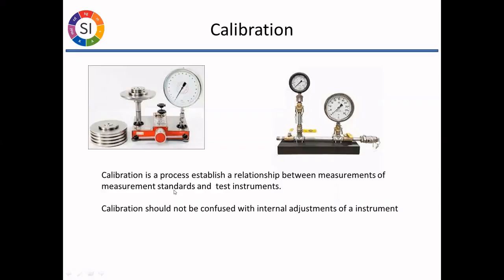We can find a term called internal calibration in the manuals of some industrial instruments. Actually, it is a self-internal adjustment. So we should not confuse it with calibration. After calibration, we get a calibration certificate that shows indicator values of the testing instrument traceable to SI units through an unbroken chain of calibrations. The measurement values consist of the quantity value, its unit, and the associated uncertainty of the measurement.